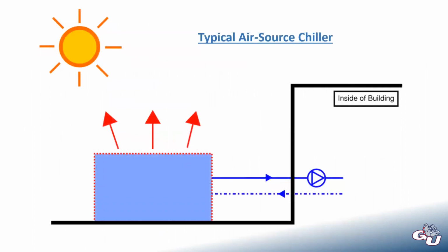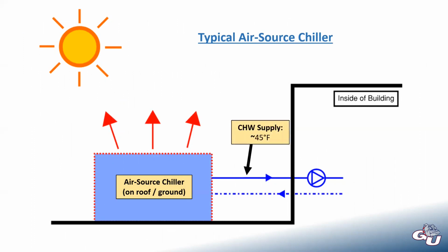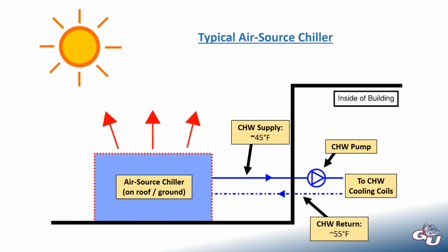A little sketch to show what this looks like. If it's not clear enough already, we have our air source chiller that's going to be on the roof or the ground, has to be outside, sending our chilled water supply through our chilled water pump that's going to go out into the building to all of our chilled water cooling coils. Then it'll come back a little bit warmer, go back into the chiller where it ultimately rejects that heat outside.